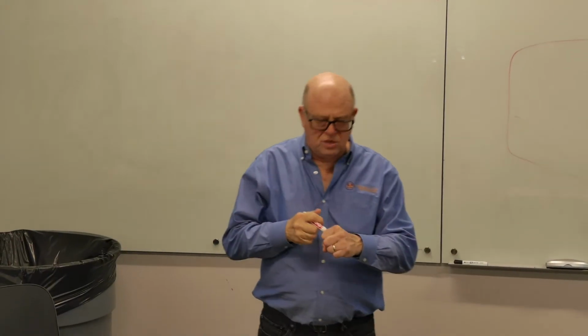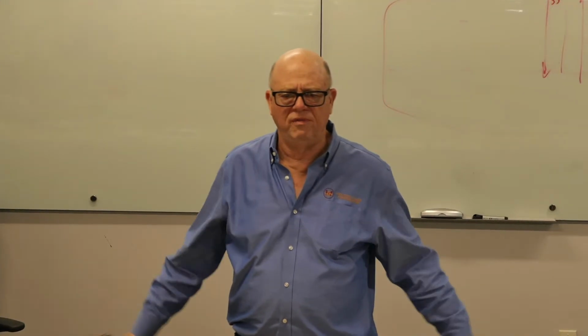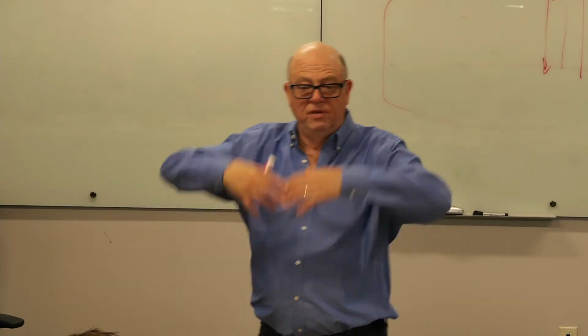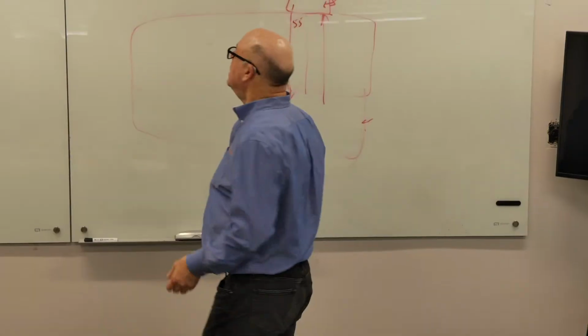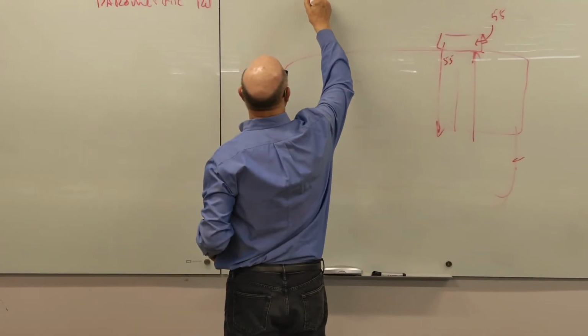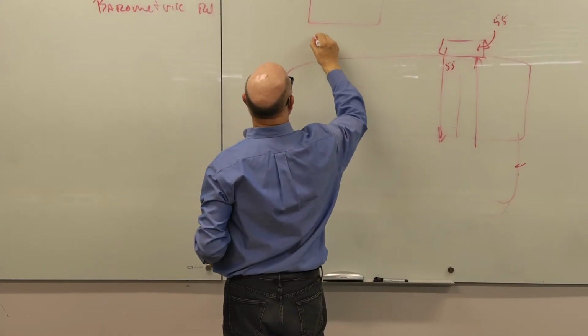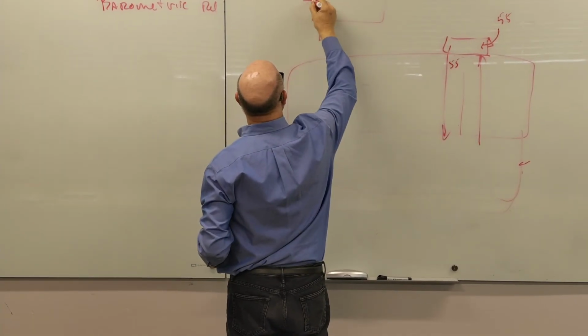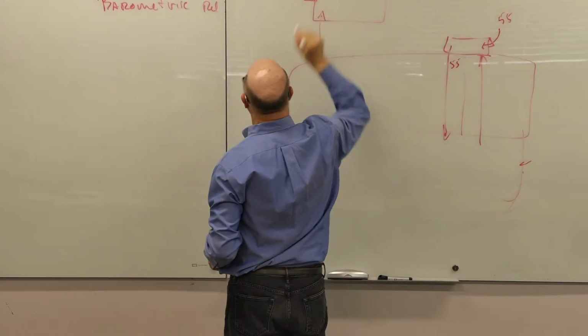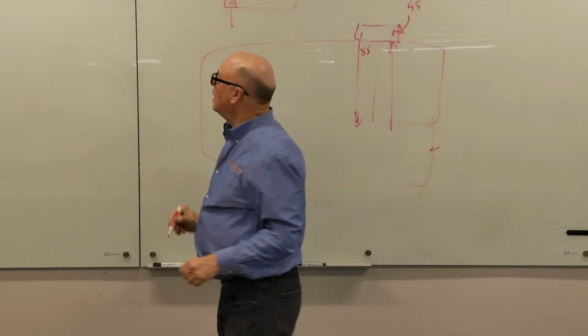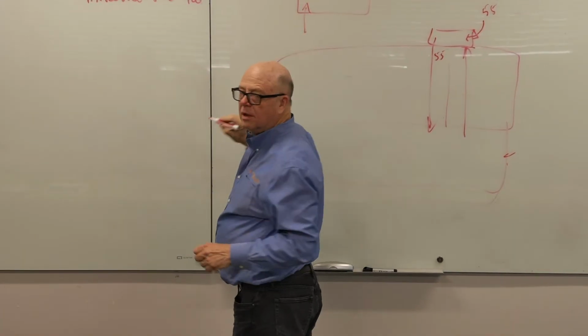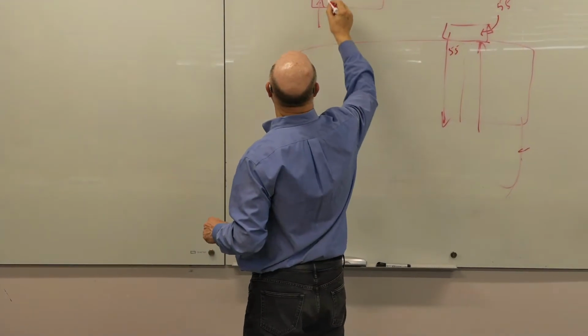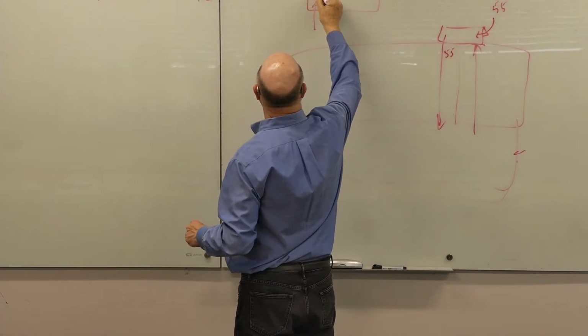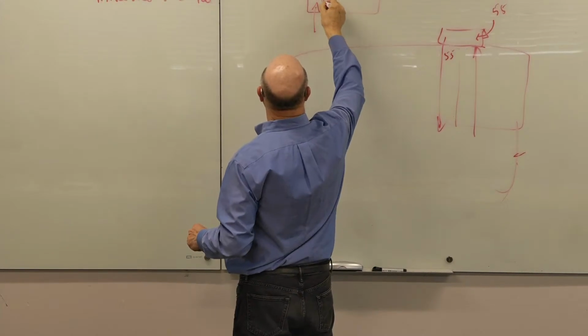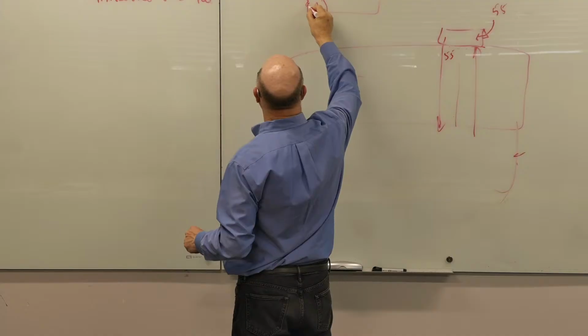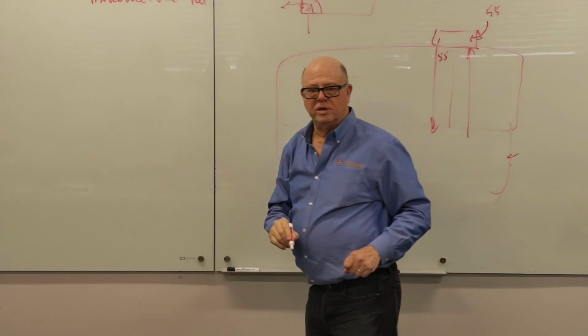Why are we, and we're going to use this term a lot, why are we calling it relief? What are we relieving? Pressure. Because we're relieving that supply air out, right? Okay, so the barometric relief in an economizer does something like this. Here's the rooftop unit, and here's that return opening we were talking about, and here's our outside air inlet with a screen over it, and maybe there's even a filter. When we go into economizer mode, we've also got in here a damper setup. And these dampers close, and these dampers open, and now the return air does that.